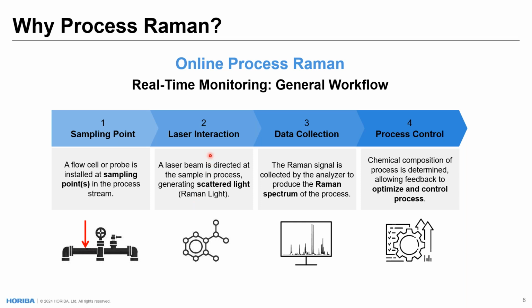Next, after the process stream is interfaced with the probe, a laser beam is turned on and directed at the sample in process, and we generate that scattered light. We look for the inelastic scattering of the molecules, which generates our Raman signal. Then that data is collected: the Raman signal is collected by the analyzer to produce the Raman spectrum of the process, sent directly into our analyzer. And then last, process control. The chemical composition of the process is determined through chemometric modeling, which allows feedback through things like advanced process control software to optimize and control the process.